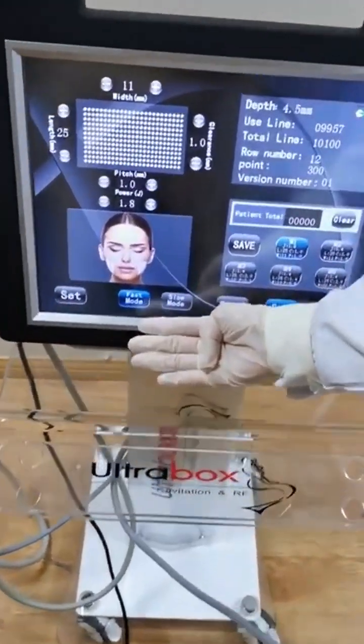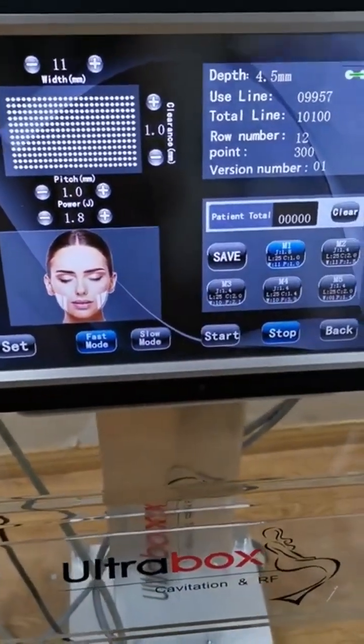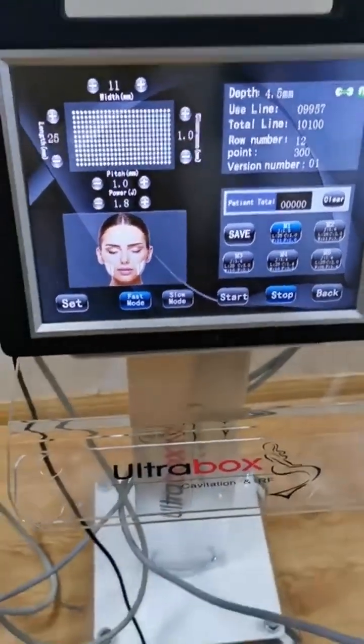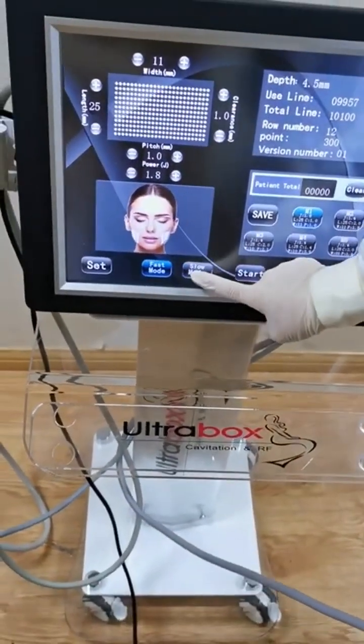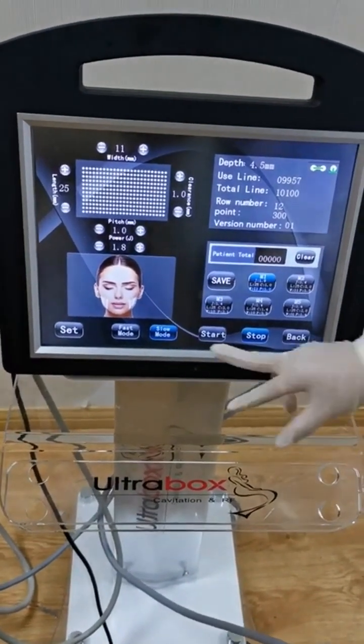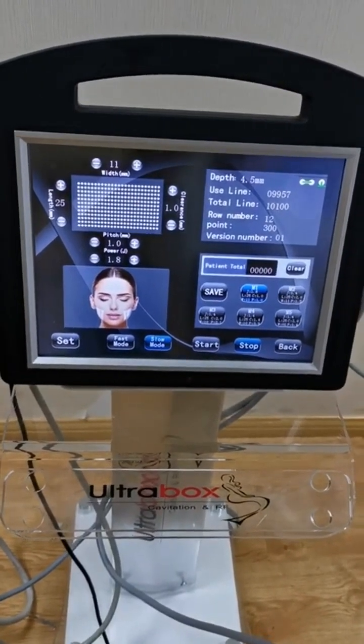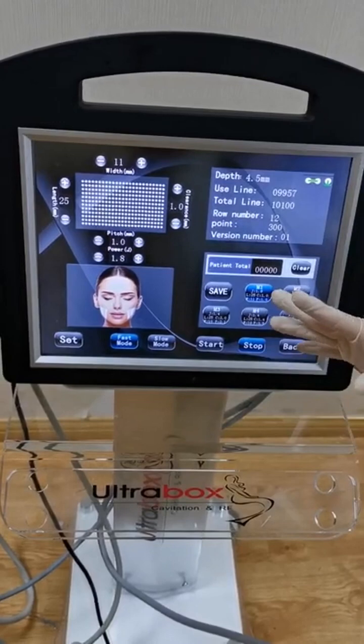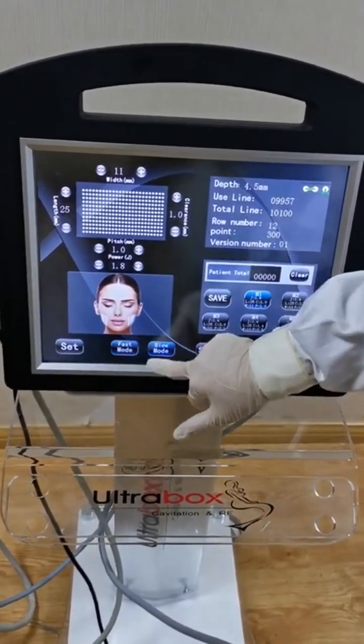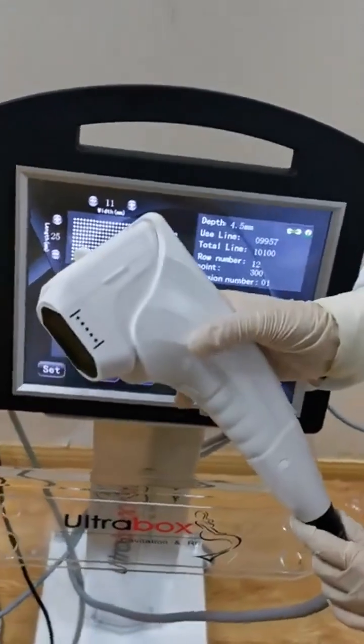It has a fast mode and slow mode for point shooting. If you choose fast mode, the point shooting will be fast. Slow mode will be slower — it is less painful. Fast mode will be more painful. So you can choose between the two modes according to your patient's tolerance. This is the HIFU treatment handle.